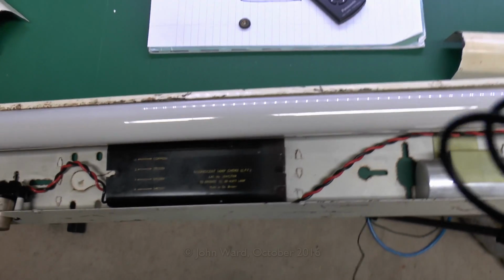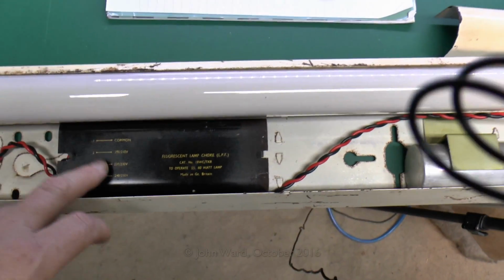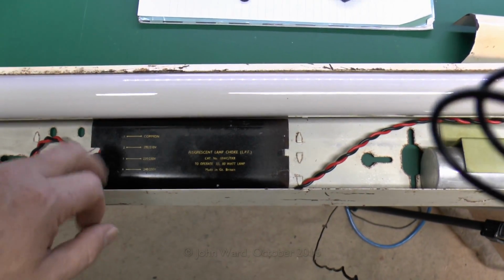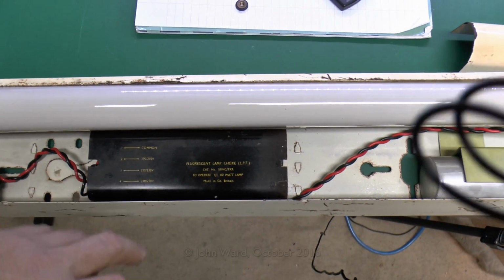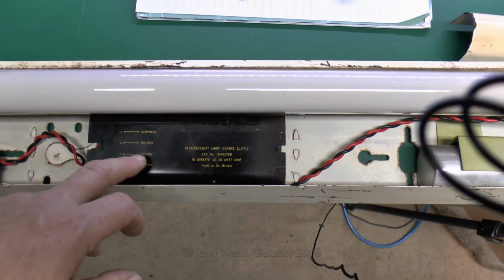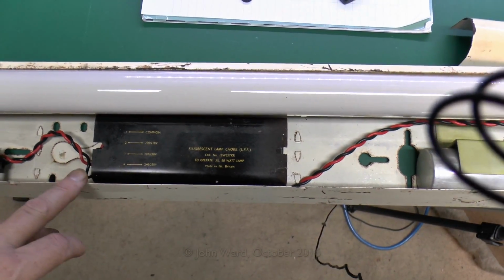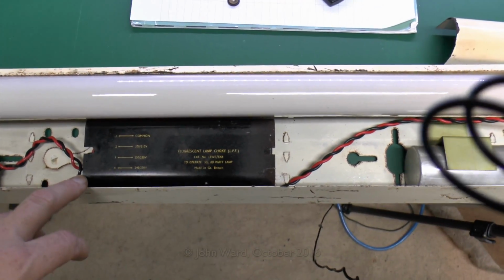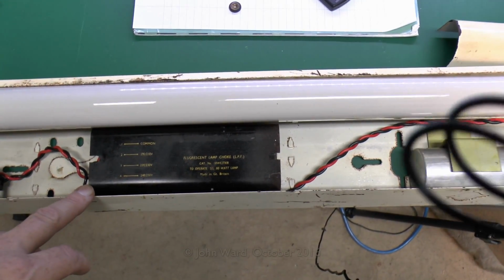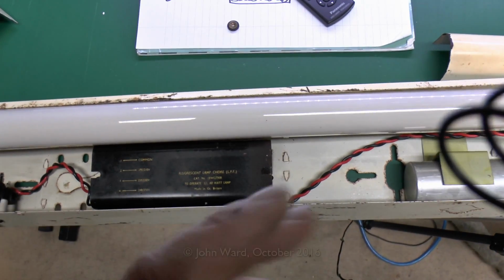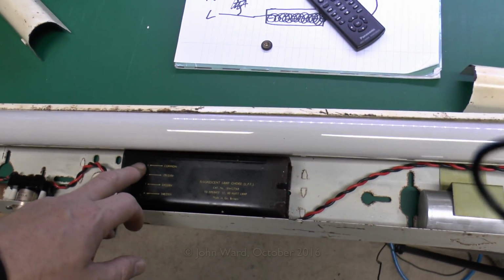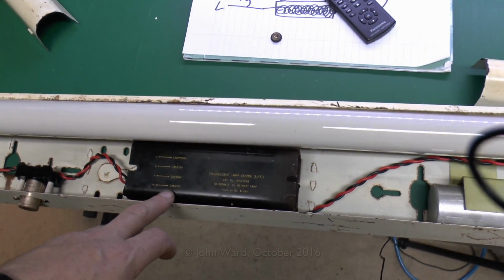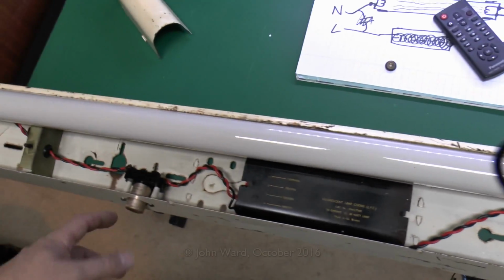Here's the choke or the ballast in this one, and this has several terminals but only two are used. It's basically just a common, and then you can pick which terminal you've got depending on the voltage wherever you are. Again, this is indicative of its age, where voltages do tend to vary in different parts of the country - it's just one terminal and then the other, say this one for 240.